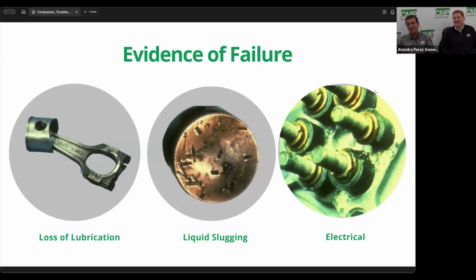So people say, I've got it in my truck. Now, what I'm saying is, okay, I'm a little short of refrigerant, and all I've got in my truck's 410A, and it takes 404 or whatever else. But also, the relief valves in these compressors are going to pop off at about 350 or 375 on the head pressure.